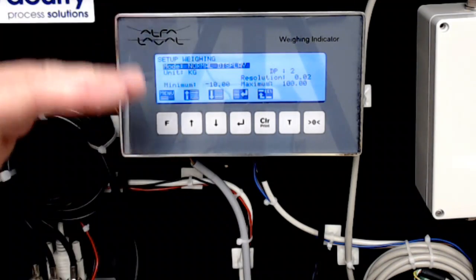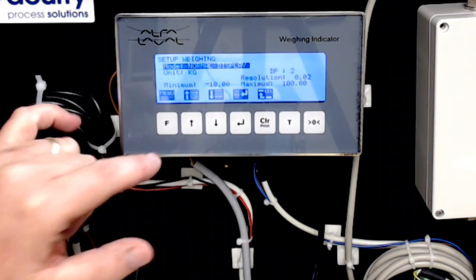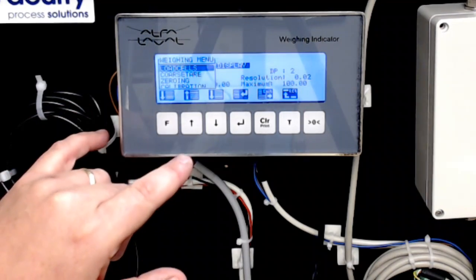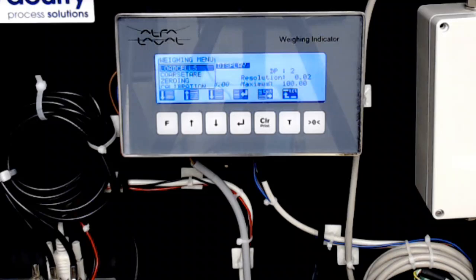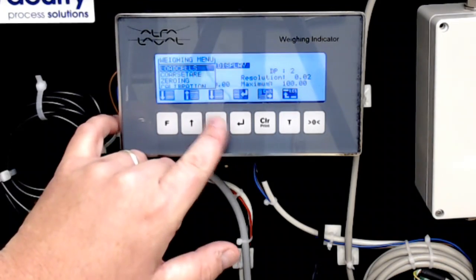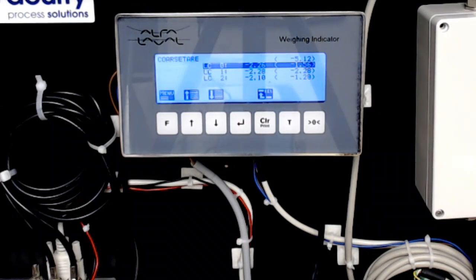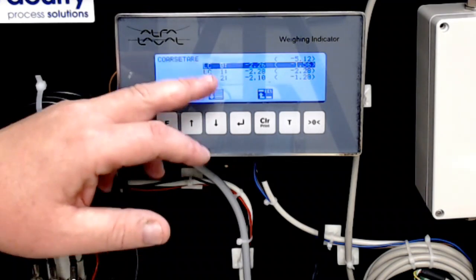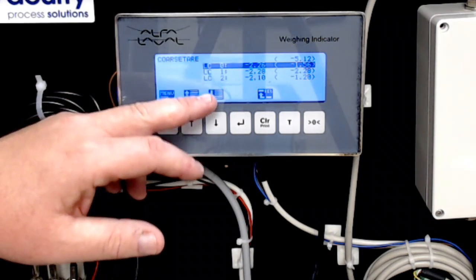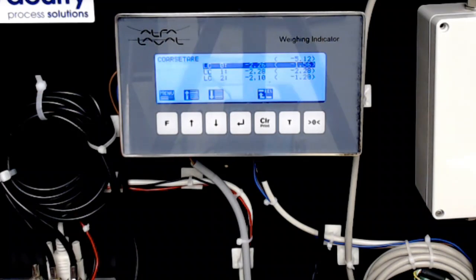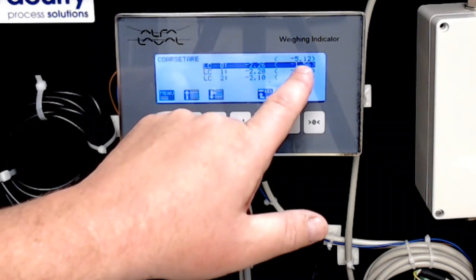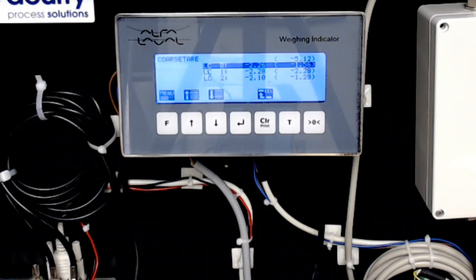Once I've entered the weighing setup, if I hit menu again, you'll see where I can get into coarse tare. If I move down to that, it's important to understand what you're looking at: in the lower section, it's seeing all 3 load cells of the system I have here, with a combined total up at the top right. You'll note those numbers are negative.